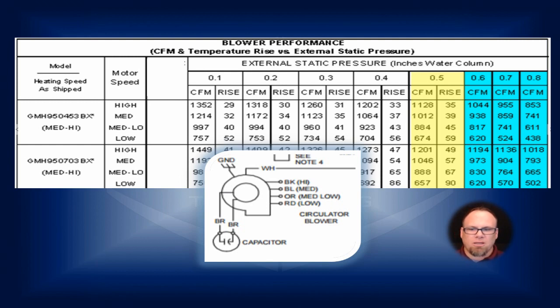Is that going to be good for every application? Do you just not set it up after that and don't need to check it because the manufacturer knows what they're doing? Well, no, that's not the case at all. That is a very specific setup that's there for the manufacturer, and the days of leaving it the way the manufacturer has it, okay, those are gone by the wayside. So you have to check it. You have to put your static pressure tubes in there, and you have to check everything. Okay, so you check before the blower and you check after the blower. And once you check before and after the blower, then you make your assessments.